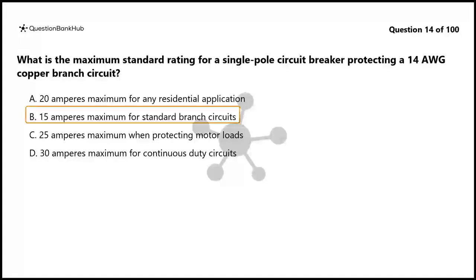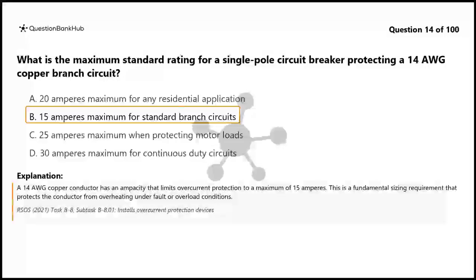The correct answer is B. 15 amperes maximum for standard branch circuits. A 14 AWG copper conductor has an ampacity that limits overcurrent protection to a maximum of 15 amperes. This is a fundamental sizing requirement that protects the conductor from overheating under fault or overload conditions.